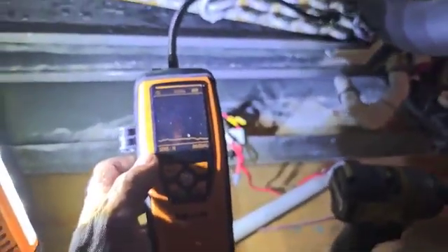Definitely somewhere in that corner. But this coil is under warranty, so that's a good job by the ILD100H. We can go ahead and confidently replace this coil.